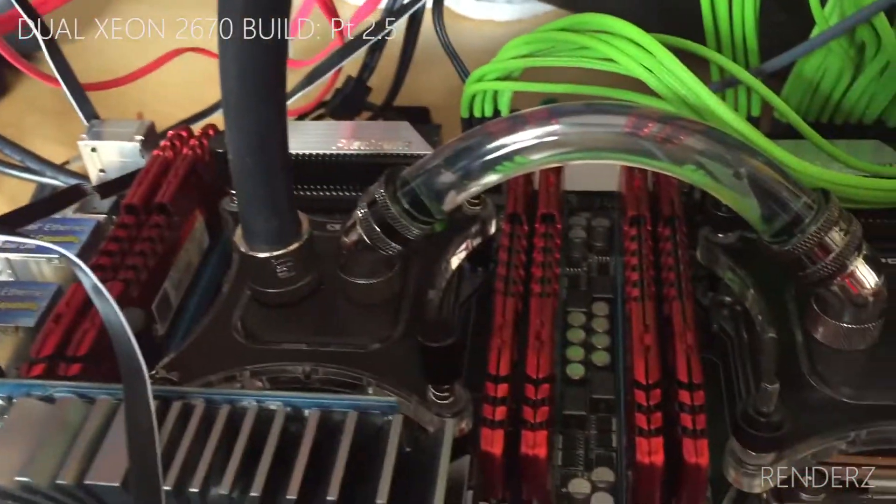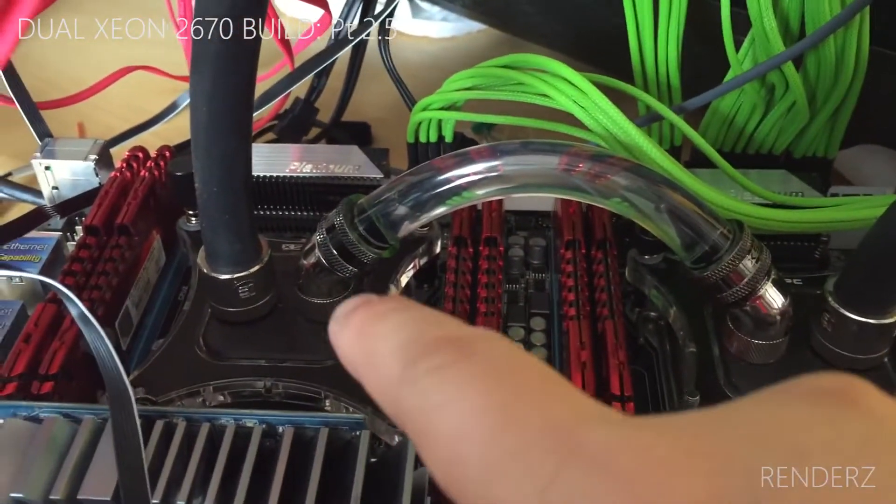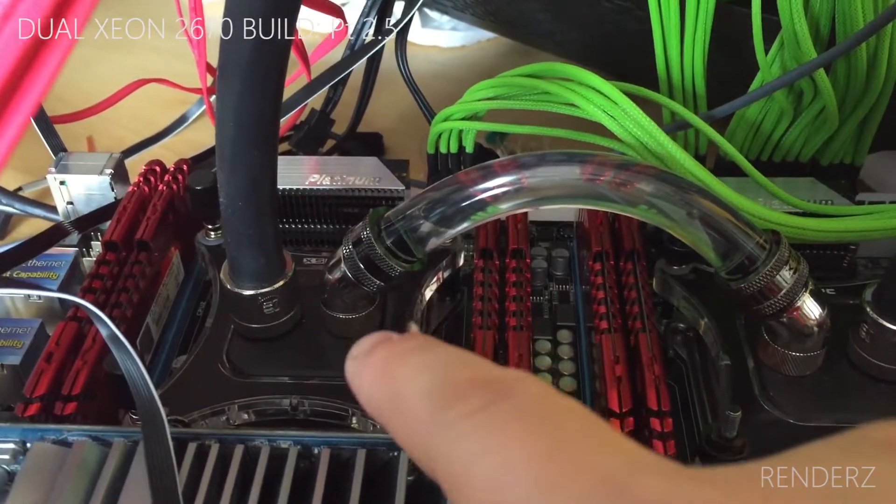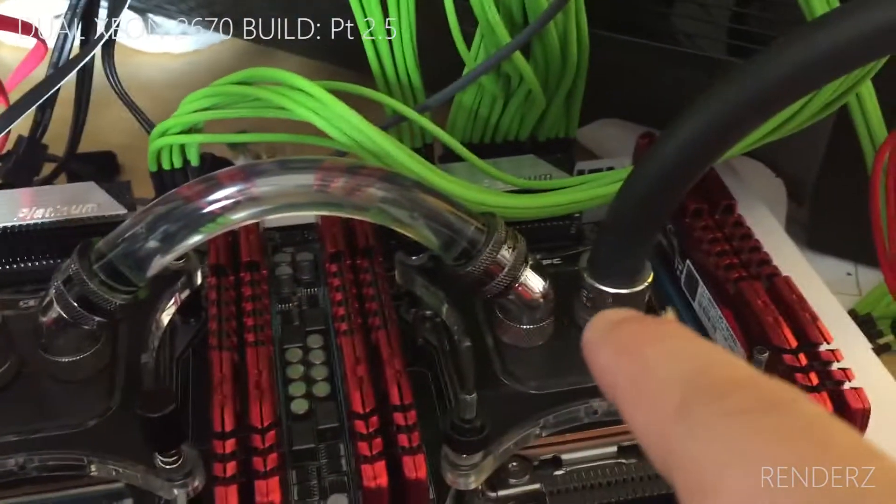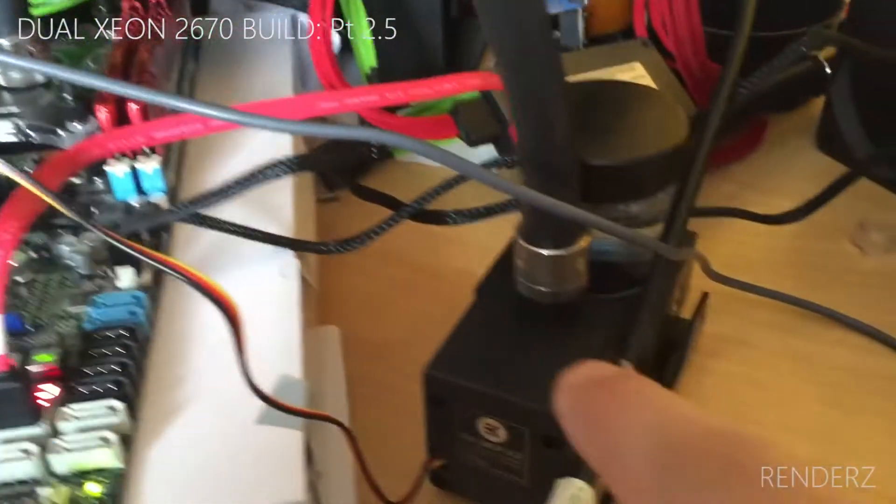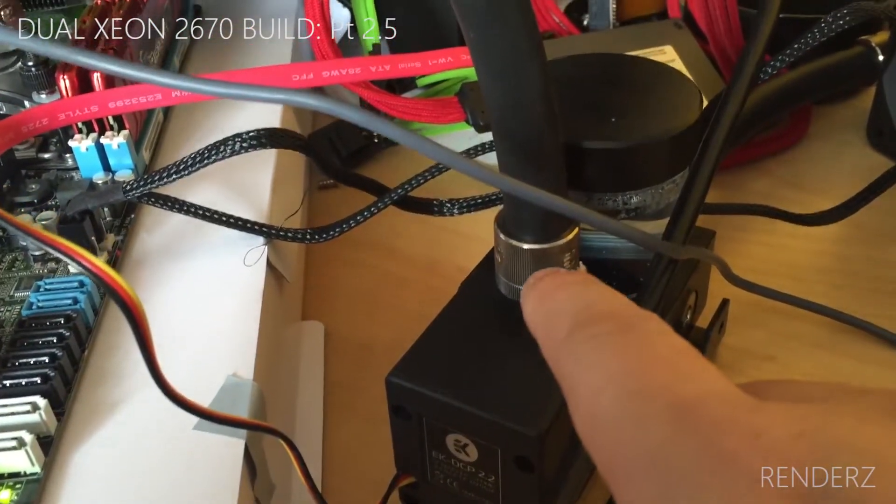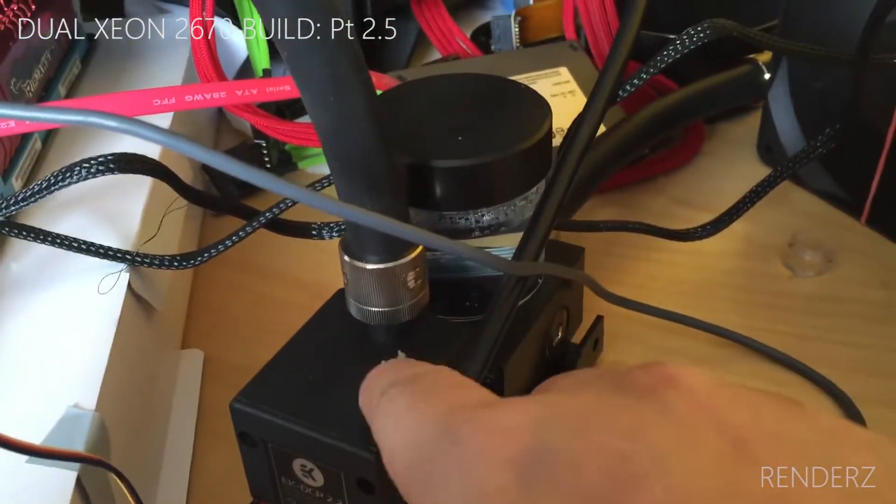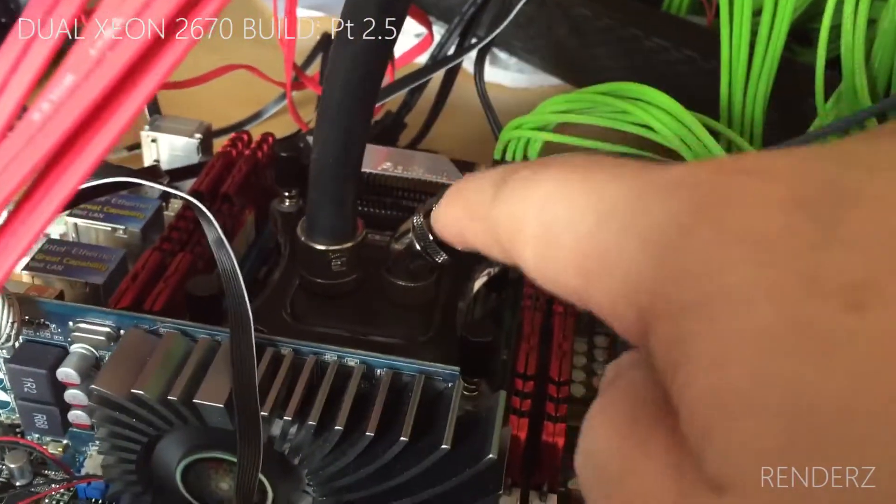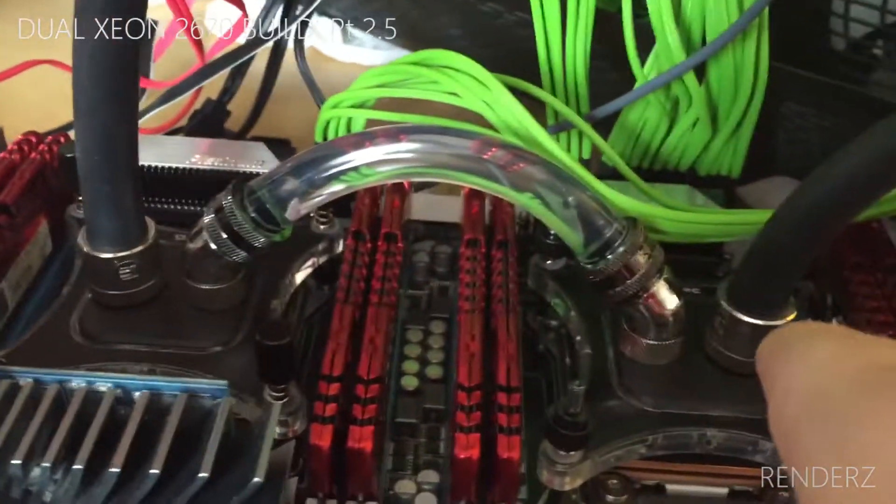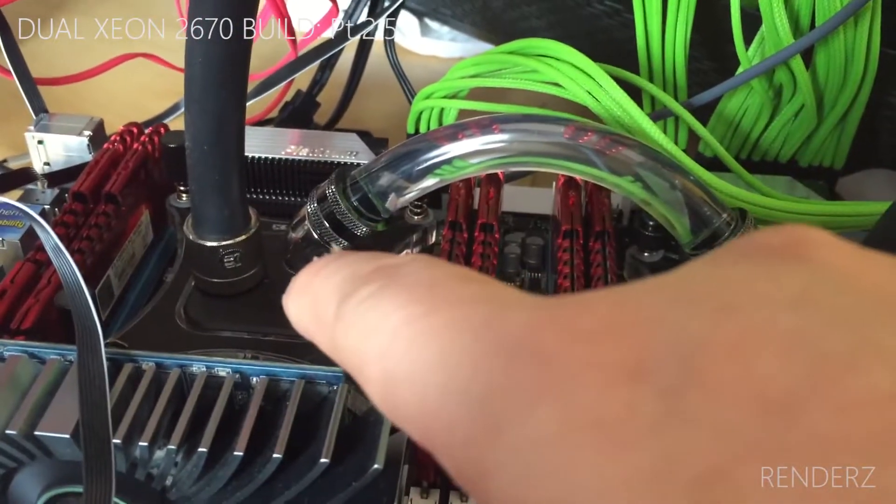Logically - I'll stop saying processor two - that's processor one, but the loop goes from here. This is the pump, this is the out. So the first processor to get the cooling is processor two, not processor one.